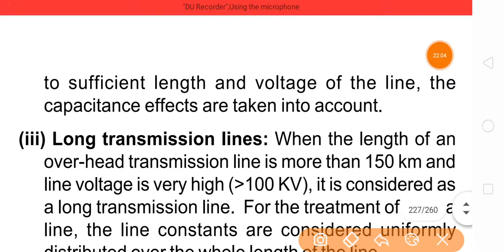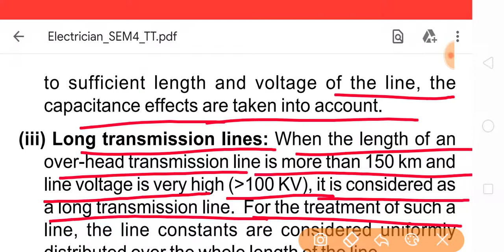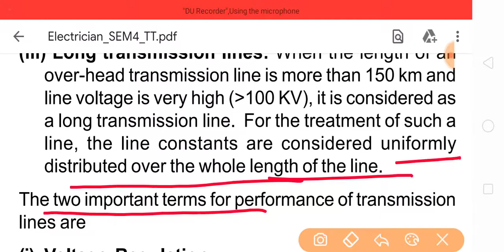Long transmission line. When the length of an overhead transmission line is more than 150 kilometers and the line voltage is very high, above 100 kilovolts, it is considered a long transmission line. For the treatment of such a line, the line constants are considered uniformly distributed over the whole length of the line. The two important terms of performance of transmission lines are voltage regulation and transmission efficiency.